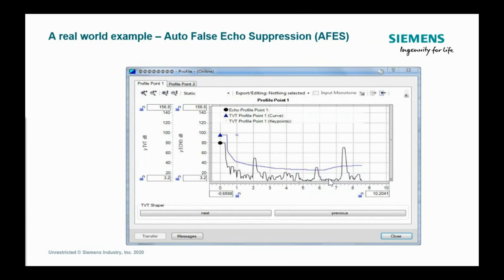And so this is the system as we found it. Again, if we had everybody live in the room, I'd say, how many valid echoes do we have? And the answer is 3. So I've got one here. By the way, this is in meters, so at about 7 feet down, I got one echo. And then I got another echo, not quite as big, exactly 10 feet later. And then there's another third echo that's 25-ish feet down, which is the true echo of the material.